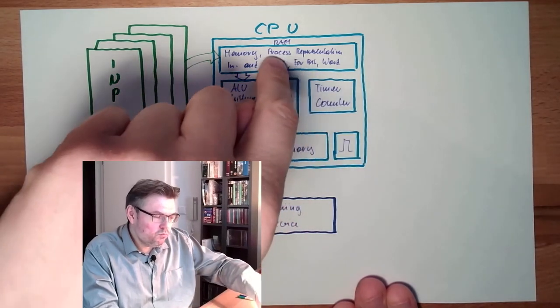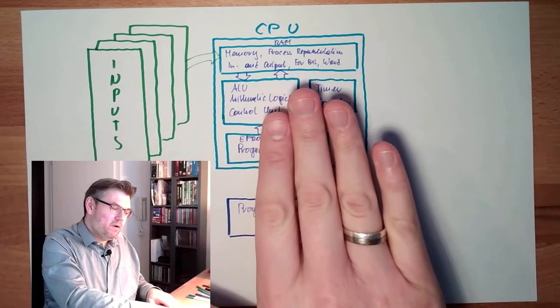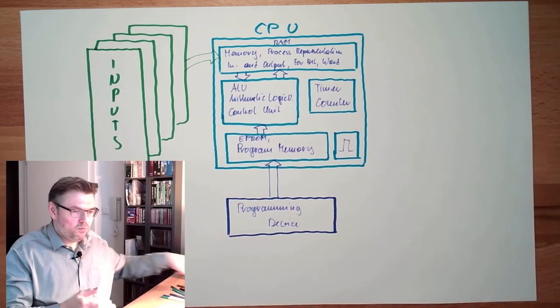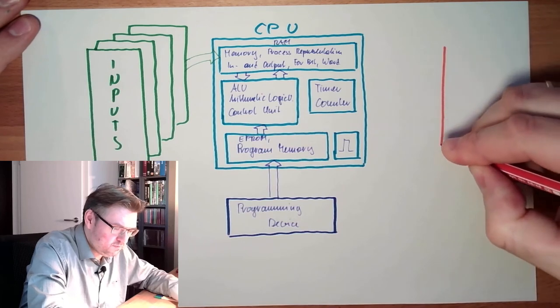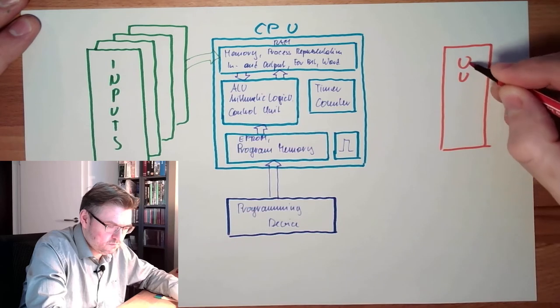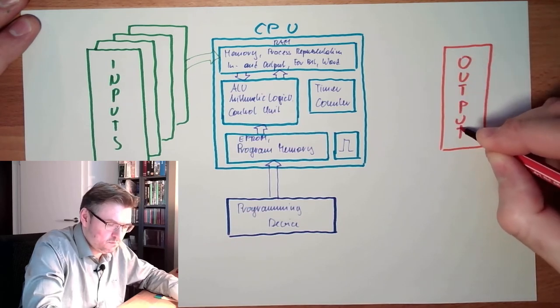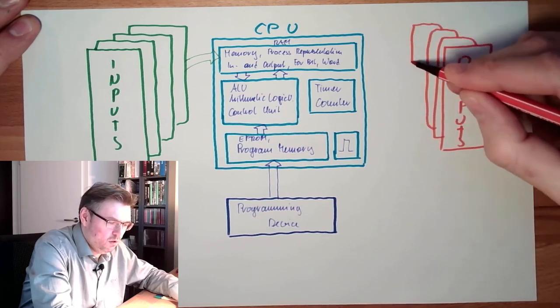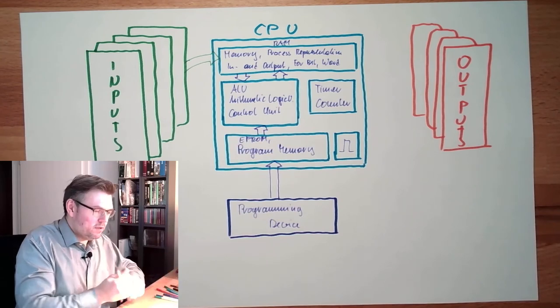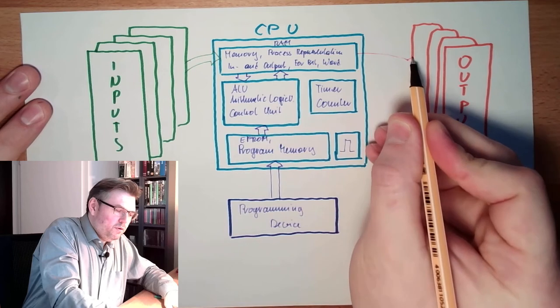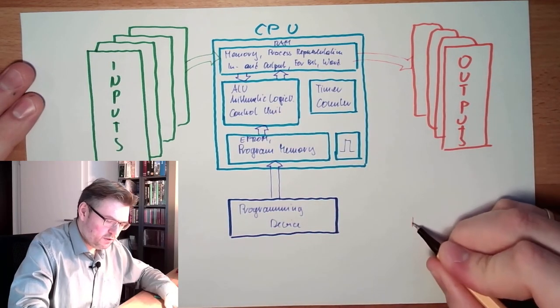Also, I will not directly write to the outputs. I will write to an output process representation in the memory. And in the end of the execution, I will copy this process representation to the output. So there are the output cards here, also more maybe, not only one. And at the end of my program execution, the process representation is copied to the outputs.